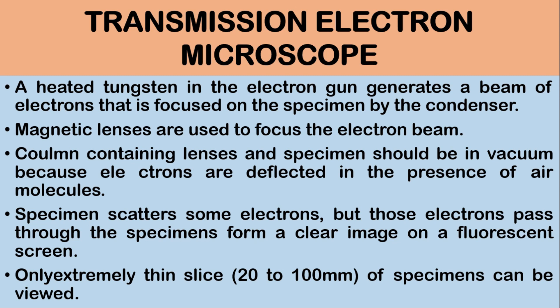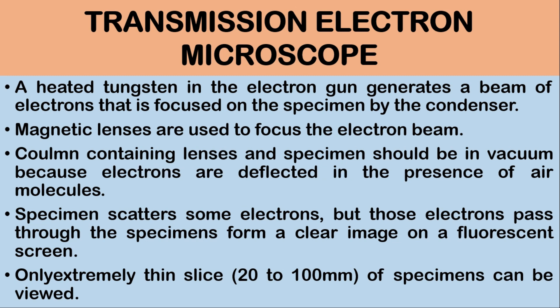Transmission electron microscope. A heated tungsten in the electron gun generates a beam of electrons, which is focused on the specimen by the condenser. Magnetic lenses are used to focus the electron beam. The column containing lenses and specimens must be in vacuum, because electrons are deflected in the presence of air. Specimens scatter some electrons, but those that pass through the specimen form a clear image on a fluorescent screen. Only extremely thin slices — 20 to 100 nm — of specimens can be viewed using the transmission electron microscope.